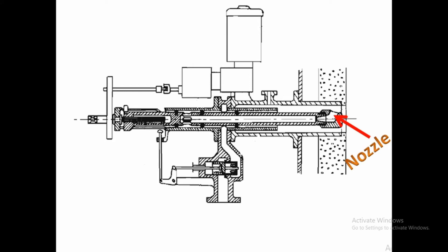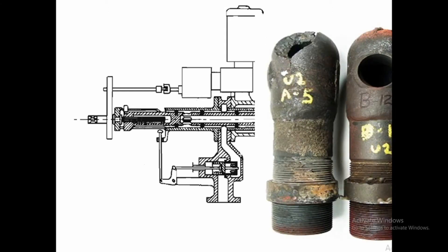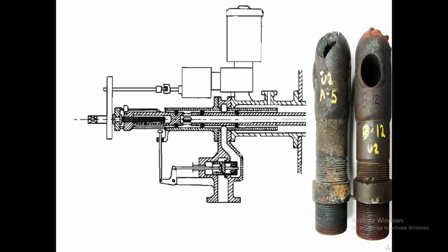The nozzle of the soot blower incorporates a passageway having a converging segment between its entrance and most narrow point and the throat. Extending from throat to nozzle exit is an expansion chamber to which cleaning fluids, meaning superheated steam passing therein, expands and drops the pressure. As a result, in a high velocity jet of fluid impinging upon the sooted surface.